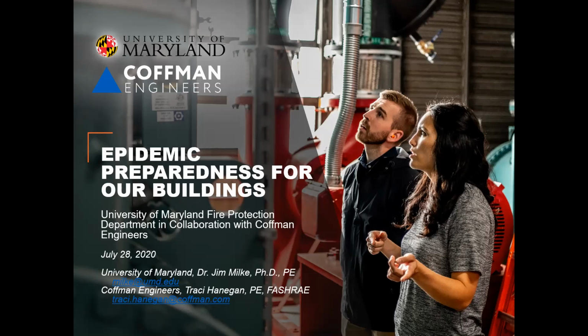Looking at that VFD capability, the incremental cost to change that is not that significant. We do need to pay attention to get good selection, so fans and pumps are running in their most efficient range, but we can build in that extra surge capacity. Some people don't think about doing it because, well, what's the point, it's just going to add extra money. But it could be really helpful in a pandemic, and the added cost might not be that significant. So I think we'll see more people evaluating that option and offering it to clients.